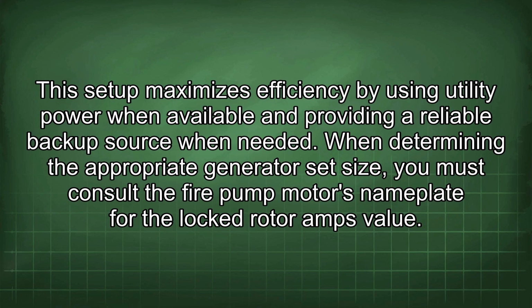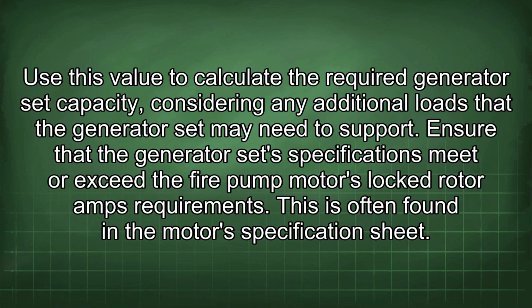When determining the appropriate generator set size, you must consult the fire pump motor's nameplate for the locked rotor amps value. Use this value to calculate the required generator set capacity, considering any additional loads that the generator set may need to support. Ensure that the generator set specifications meet or exceed the fire pump motor's locked rotor amps requirements. This is often found in the motor specification sheet.